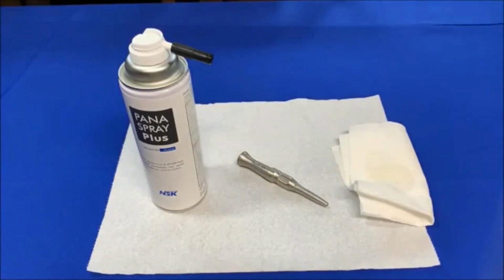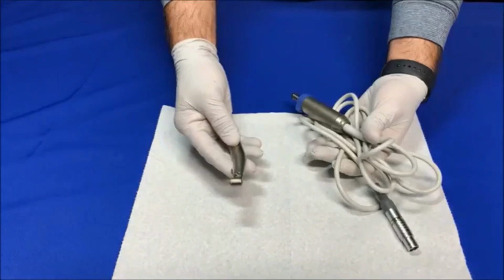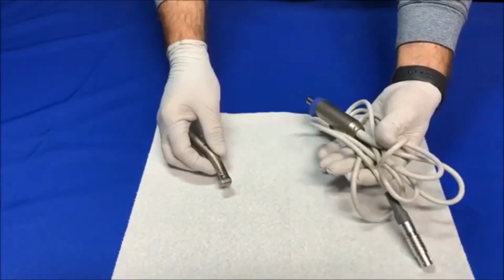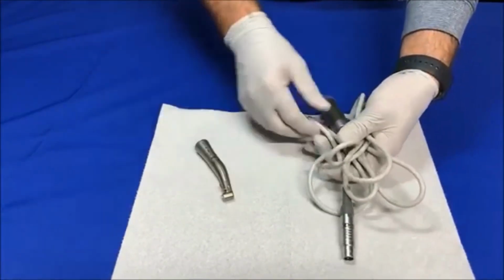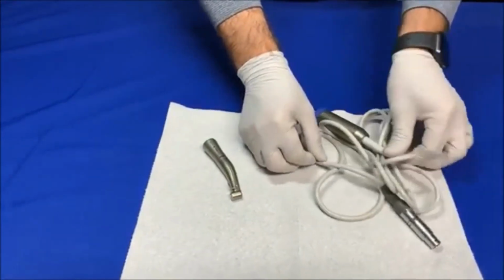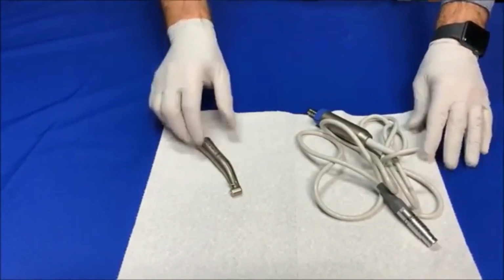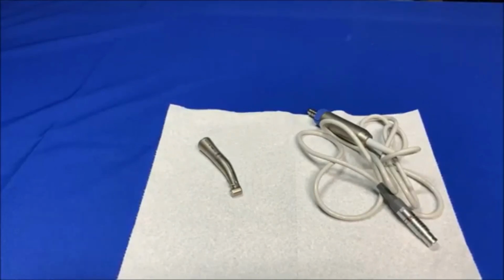The entire motor and its cord is autoclavable, so is the attachment. But the motor and the cord do not need to be lubricated. Place the handpiece and the micromotor in separate autoclave pouches and seal them before putting into the autoclave.